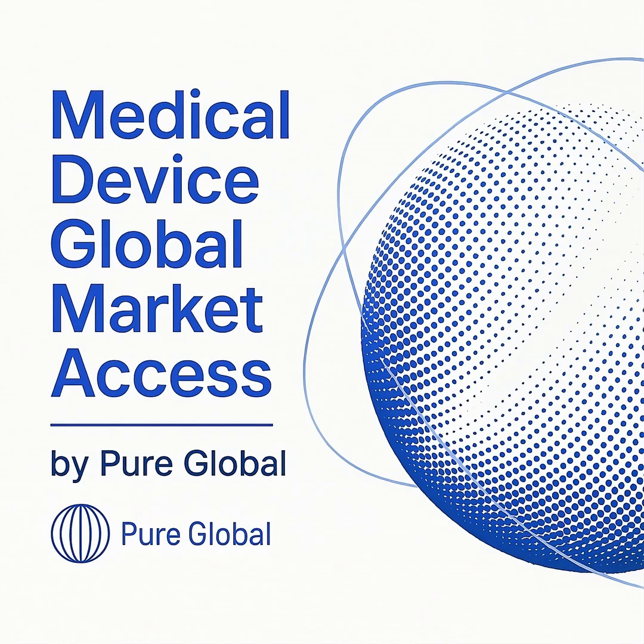Under the Medical Devices Rules 2017, India has established a comprehensive framework for market access. The first and most critical step for any foreign manufacturer is to appoint an Authorized Indian Agent, or AIA. This local entity is legally responsible for your device in India. They hold the import license, manage all communications with the CDSCO, and handle post-market surveillance activities, including adverse event reporting. Your company cannot directly apply for the license without this local representation.